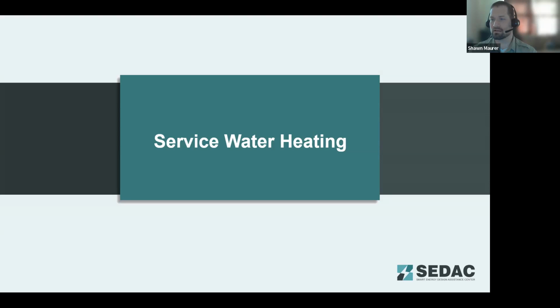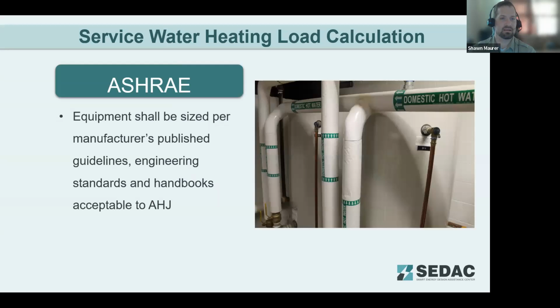Okay. We'll go into service water heating differences, comparing ASHRAE and IECC here to wrap up our presentation. So first thing is service water heating load calculations. Similar to building HVAC, it's important to properly size your service water heating equipment. So ASHRAE has included a requirement for that. That equipment shall be sized per the manufacturer's published guidelines, an engineering standard and handbook, or other calculation method acceptable to your authority having jurisdiction.